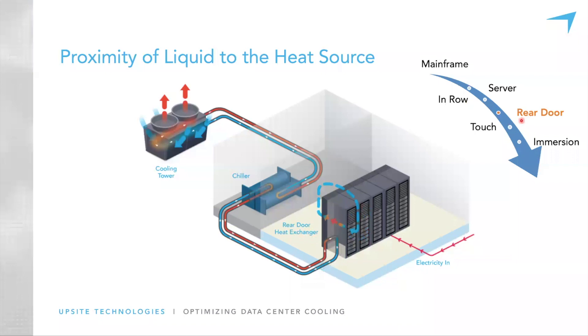The next step is rear door heat exchangers, where liquid is now on the back of each cabinet. A rear door heat exchanger is mounted on the back of each cabinet and is often referred to as a liquid-cooled solution. However, it is not truly liquid cooling because liquid is not removing the heat from the source — air is still removing the heat from the source and only carrying it a couple of inches before passing the heat to the liquid flowing through the radiators in the rear door.